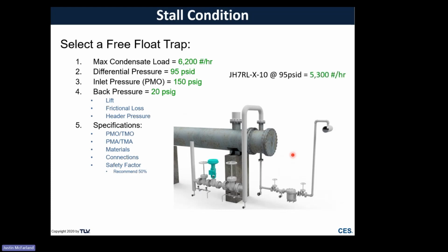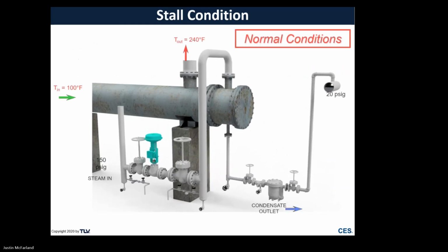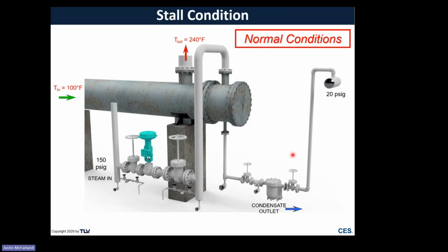So one of the exercises I would take through my class, typically if we've got some more time, is I would have them pick out the TLV steam trap. So in this case, it would actually be this particular model you see right here. So that was the full load scenario. Now we've got a normal load scenario. So process temperatures are the same, but now we've got a slightly reduced flow rate, which corresponds to a slightly lower steam flow rate because we need less BTUs. And we've got less pressure as well. It's going to end up in a lower positive differential pressure. Again, we can still size the steam trap.